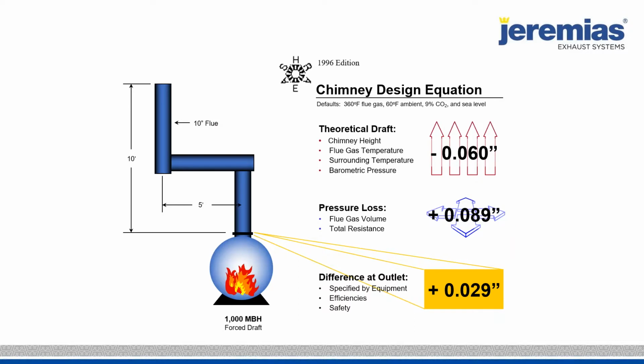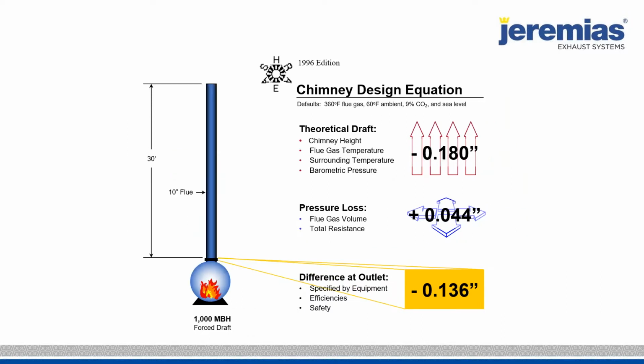Here we added 5 feet of horizontal, a couple fittings, draft stays the same, pressure loss increases a lot. So when you do the math, you're now measuring a positive vent pressure at the outlet. That means you're having flue gases spilling out of the barometric damper, or the combustion is now changed. You don't have as much excess air.